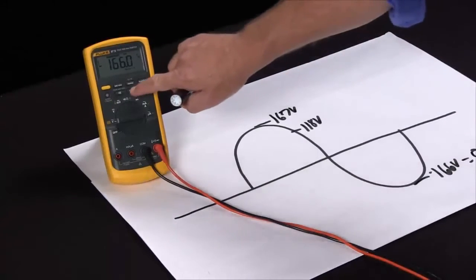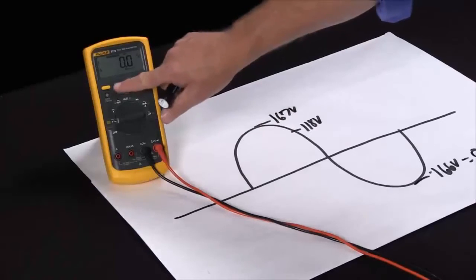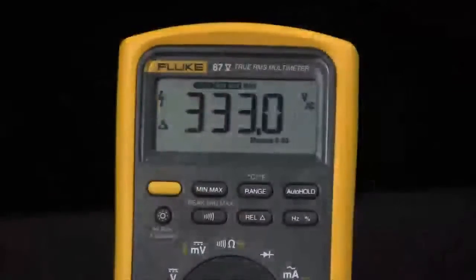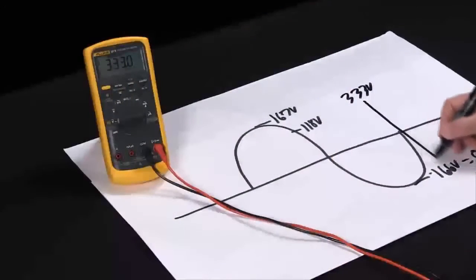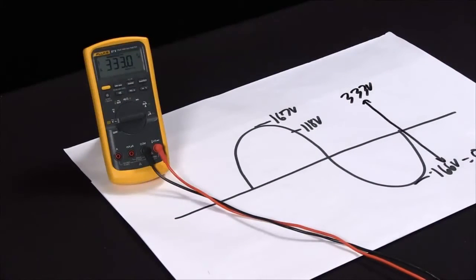So if I hit relative, that becomes zero, and now I'm measuring the peak to peak of 333 volts of this sine wave by using a combination of the fast min max and the relative mode.